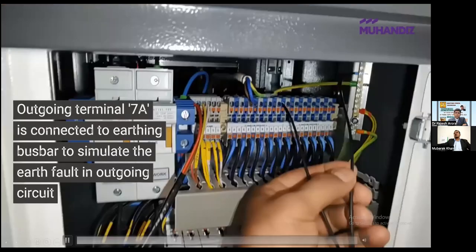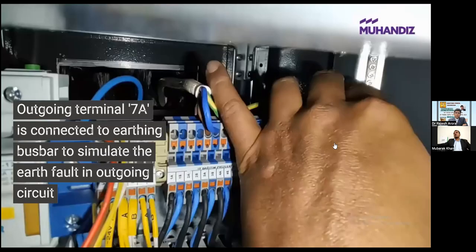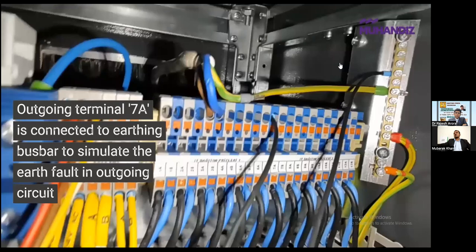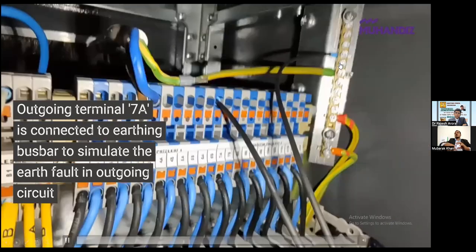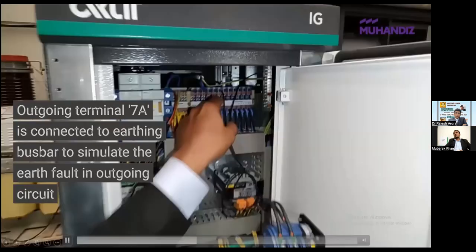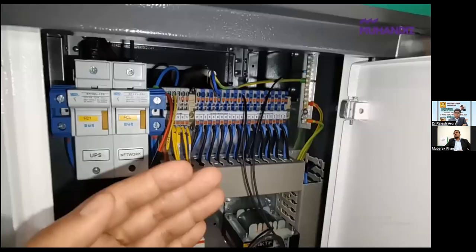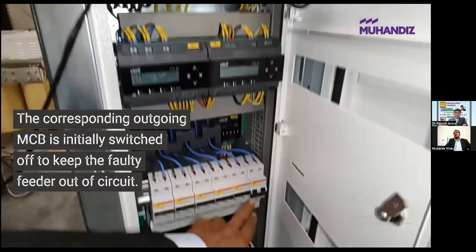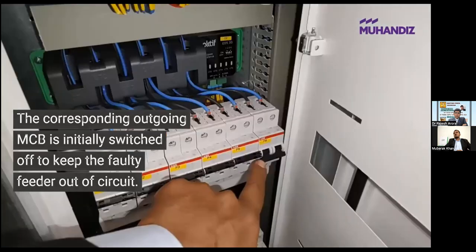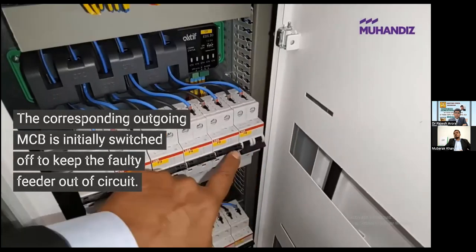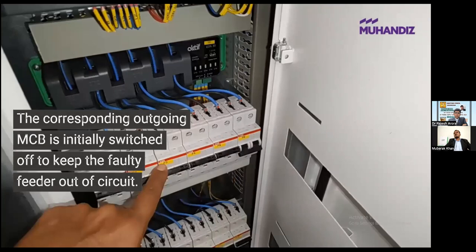Now, just to simulate an earth fault, I have connected one of the outgoing cables to the earthing circuit. Okay, just to simulate an earth fault so that we can create that earth fault and see it. So that particular feeder I have kept off. So when I switch it on, the alarm should come. Okay, in this way I have simulated the earth fault.